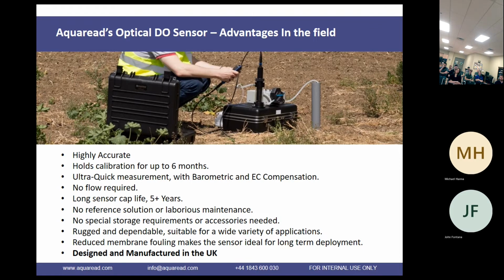With a galvanic sensor, you need a steady flow of water over it because it's a chemical reaction sensor. This is an optical sensor, so it uses light, meaning you don't need any flow. There are no special storage requirements either, so you don't need to remember to fit a container with water to keep it moist - this sensor can just be left dry. There's nothing in it that will degrade or dry out. It's rugged as well, performing very well in applications with a lot of fouling, because of the materials we've used.